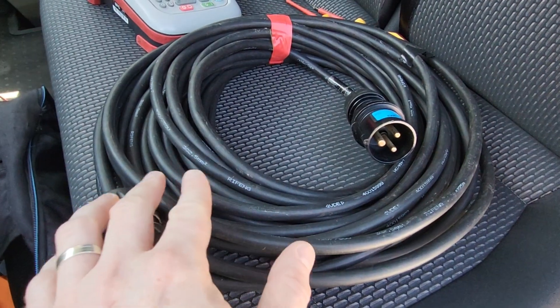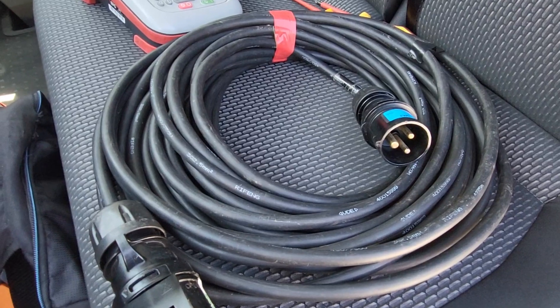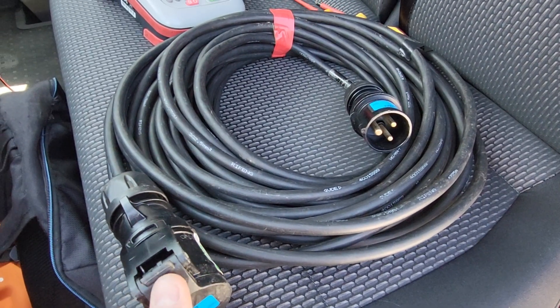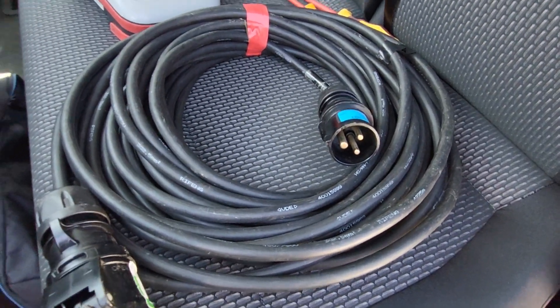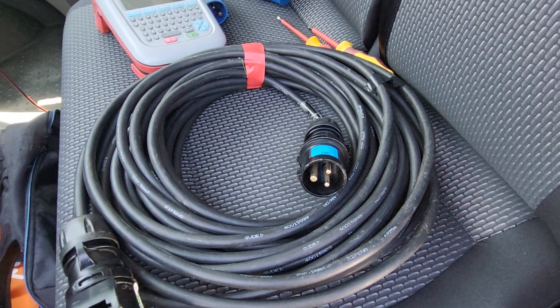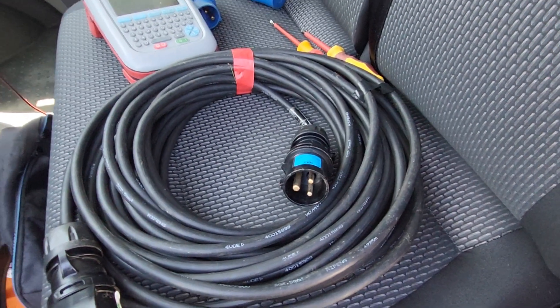You might say, well if the flex is only 1.5mm and can only take up to around 15 amp, but it has 16 amp connectors — surely that shouldn't be allowed. That's a whole other subject for another day, but it would actually be okay. It relates to system and power design and the way it's laid out, but that's a whole other subject.